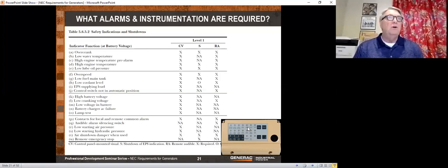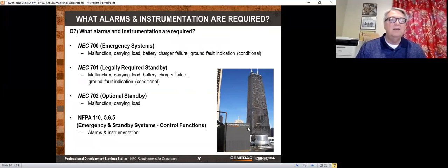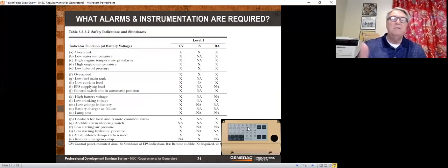Let me mention one more thing here. There are two types of generators, and I could say that in a lot of different ways. But in this case, I'm saying that there are industrial generators, and then there are commercial and residential generators. Commercial and residential generators are not built for emergency. They're not built for legally required. They are only built for NEC 702 optional standby. So they may only have a malfunction light on. I'm not saying they will. The controller could have more stuff, but it's only required to have that. And because of that, they may not even have these sensors in the generator, let alone be able to annunciate them.